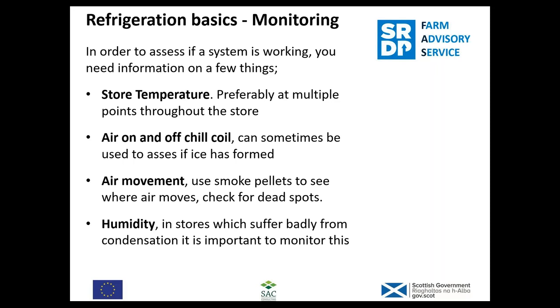Air movement — this is more of a check than monitoring, but it's really useful: smoke pellets. If you've got a chimney, you'll often get the sweep to test your flue with a little smoke bomb. Those are really useful for telling where airflow is — you can release them whilst the ventilation system's on and see where the air flows. It can be very useful for checking dead spots. Humidity is quite useful in cold stores. If they suffer badly from condensation, or if your potatoes or any product is getting quite a lot of condensation, it's good to know how close you are to the 100% humidity or saturation point — it's a very easy, simple thing to monitor.